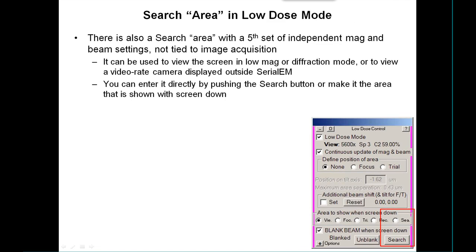There's also a thing called the search area, which has another set of independent magnification and beam settings but is not tied to an image acquisition. It can be used if you want to look at the screen in either a standard low-mag or diffraction mode, or if you have a video-rate camera displayed outside of SerialEM. You can either enter it directly by pushing the search button or make it active by making it the area shown when the screen is down.